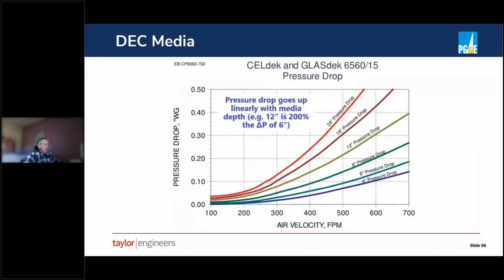But the pressure drop of the media does go up linearly. And so a 12-inch media is 200% of the pressure drop of a 6-inch media. And so you want to think carefully and run your design condition calculations to figure out what's the thinnest media I can get away with. In almost all the cases we've worked on, 6 inches is sufficient depth, even under the worst conditions in places like Nevada, Arizona, even Alabama, Georgia.